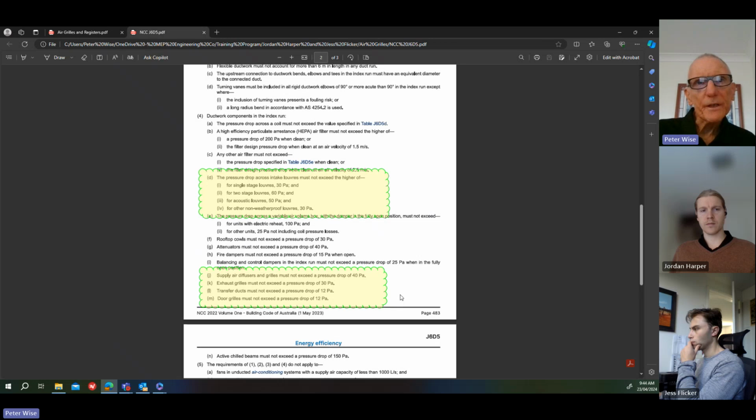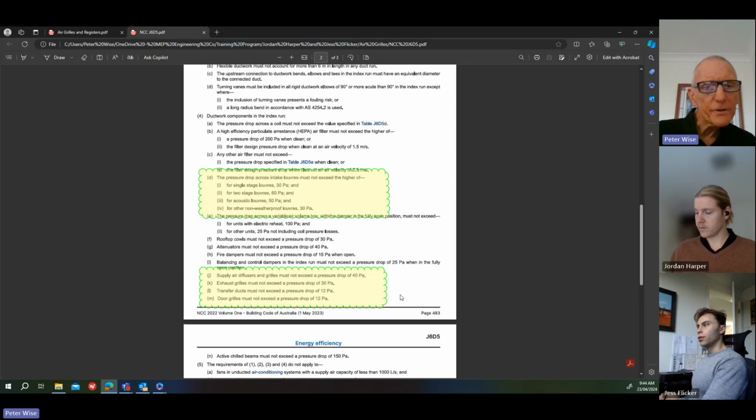So having mentioned that, with your static calcs, Jess, I think that there are defaults in the spreadsheet for these pressure drops. But if you look at it, if you do an actual selection, you can always get well below that allowance. So you don't want to go too far overboard with your calculations because you'll finish up with a number that's too high.